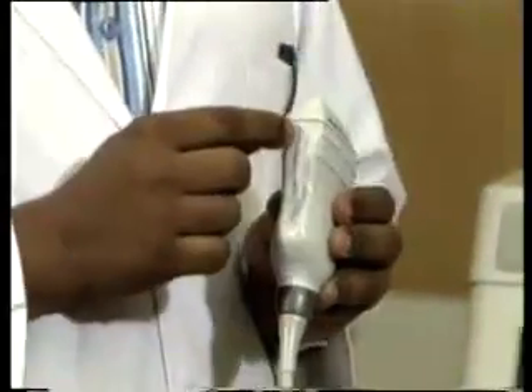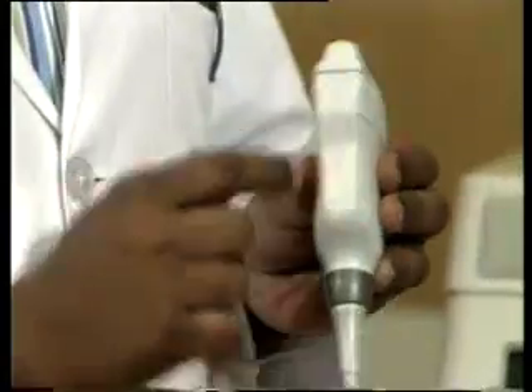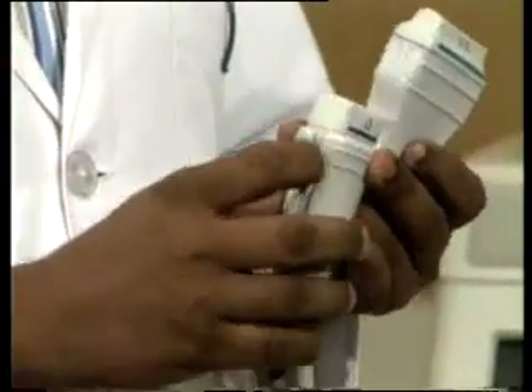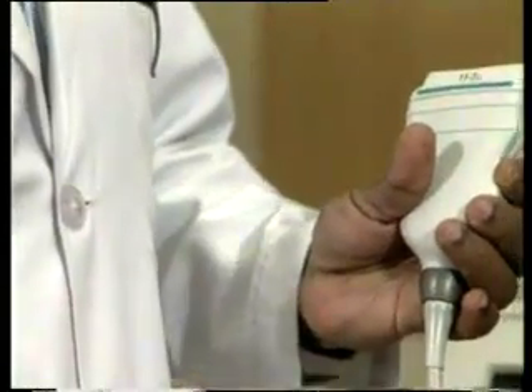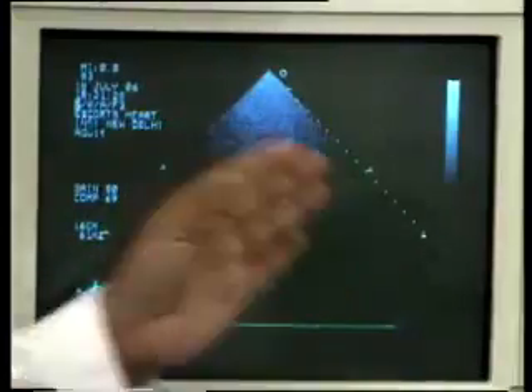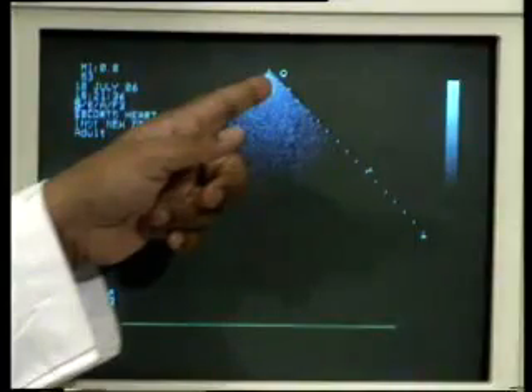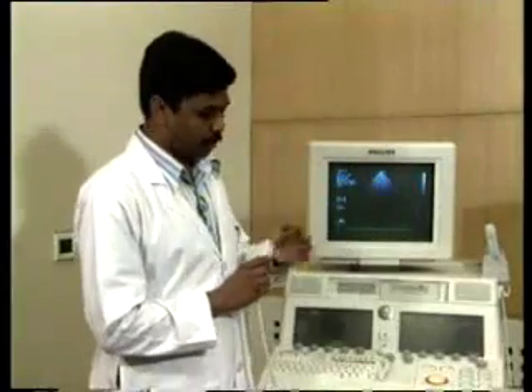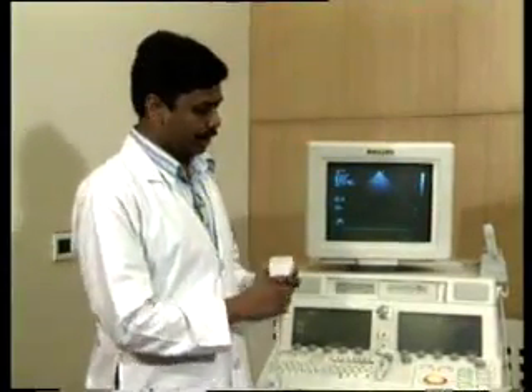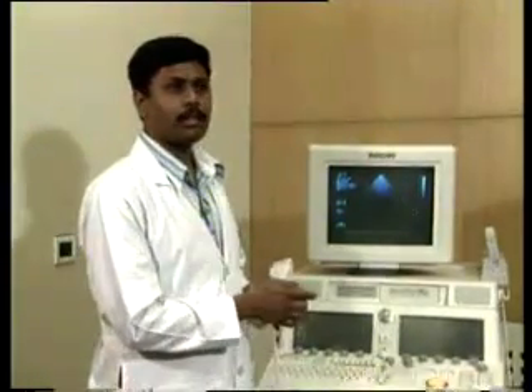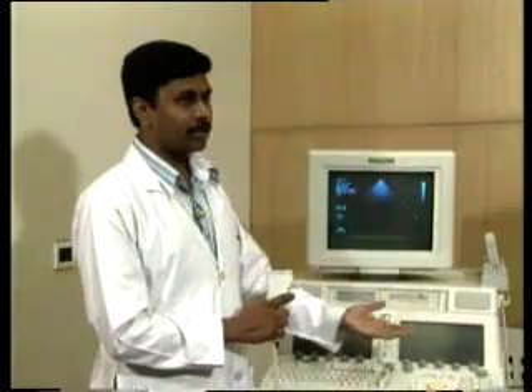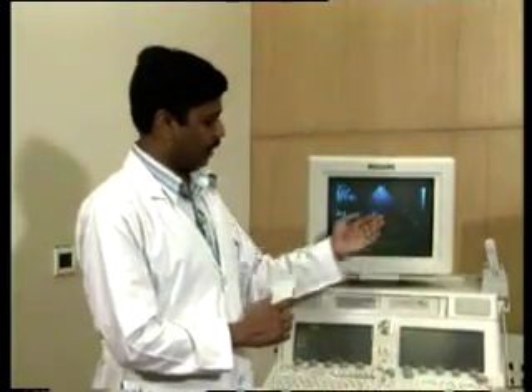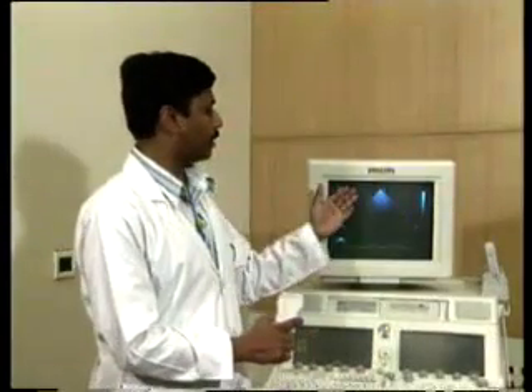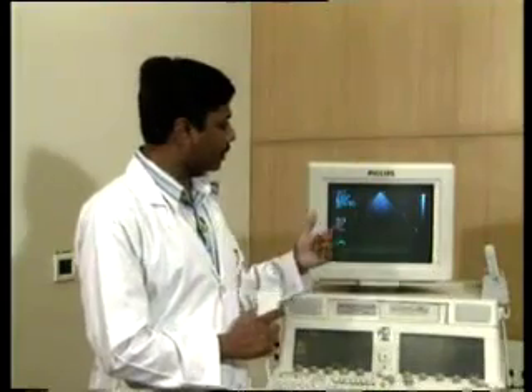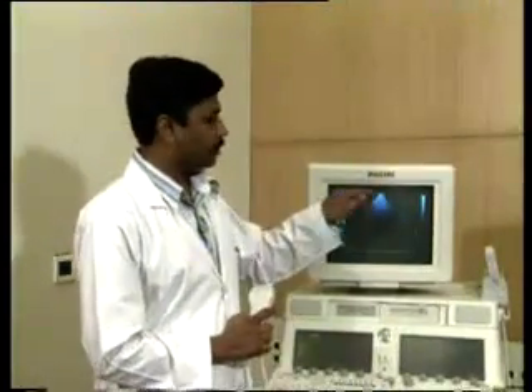All the probes have a marker on one side, like in this it is here, in this probe it is here. This marker helps in localizing the image on the screen or the monitor. This small circle denotes the side on which the marker is present on the transducer. So if we are holding the transducer like this, the marker is on this side, so structures that are present on this side of the probe are displayed on this side, and structures which are present on this side of the probe are displayed on this side. So that is how we localize the image on the monitor using this marker and this dot here.